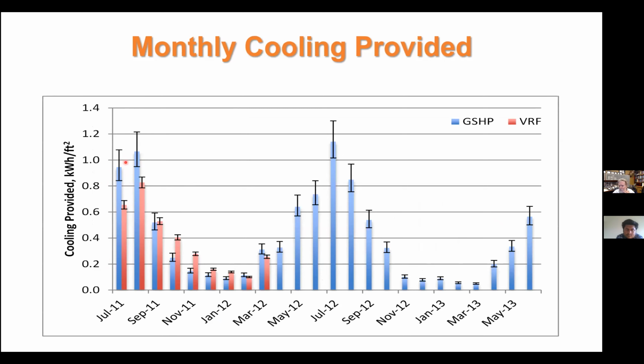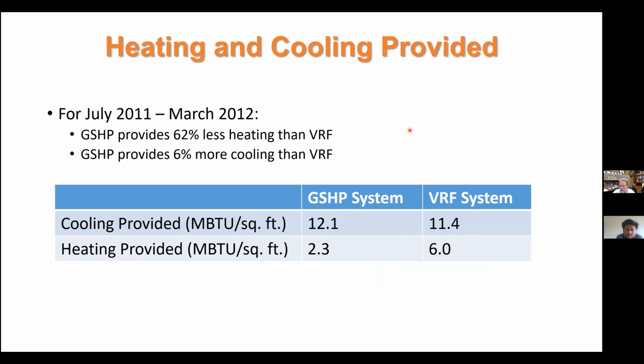The ground source heat pump system is providing more cooling in the summer months, but in the shoulder seasons, you see actually it's providing a bit less. And I think this again goes back to the thermostat. So if you look at the 9 months that we could actually compare both systems for, the cooling provided for the ground source heat pump system was a little bit more in terms of thousands of BTUs per square foot than the VRF system, and the heating is somewhat less. So there's 62% less heating than the VRF and 6% more cooling.